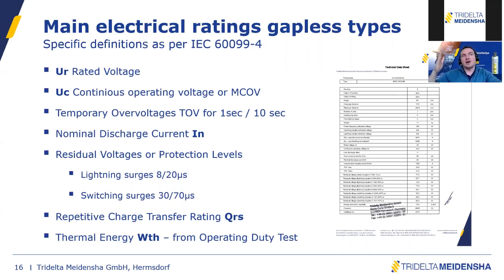We need a kind of reference, a typical lightning current, to classify arresters. Then you have, as I said, the most important characteristic or rating of the surge arrester, the residual voltage or protection level, which is related to a specific lightning impulse or switching impulse value with a specific wave shape defined by the standards. Then you have two important energy ratings that I will develop afterwards: the repetitive charge transfer and the thermal energy, Wth, coming from the operating duty test.